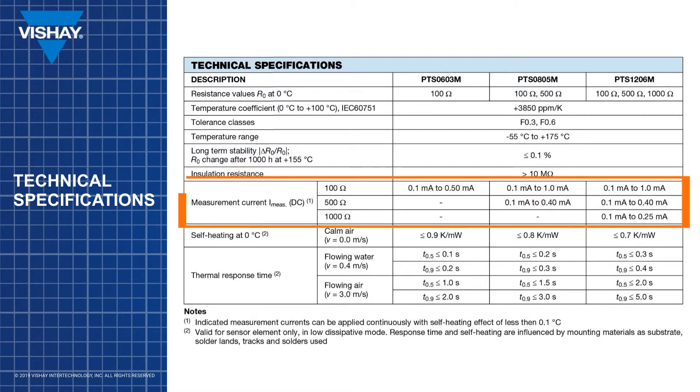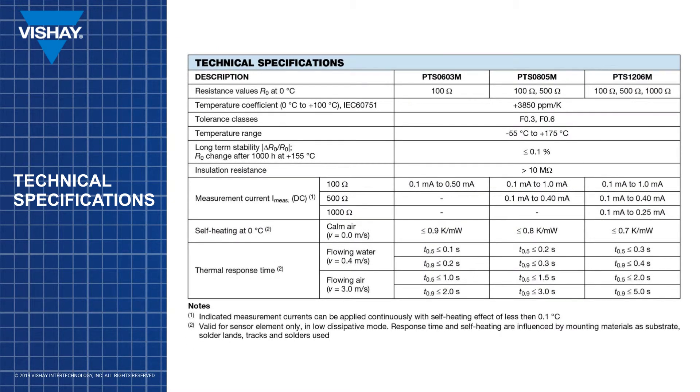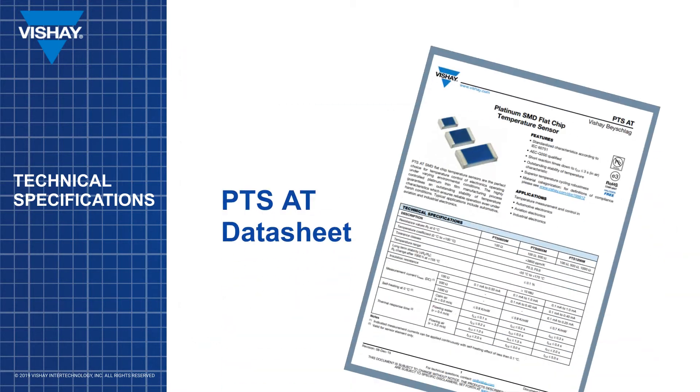The measurement current is dependent on the size and value of the sensor. The measurement currents listed can be applied continuously with minimum self-heating effects. The thermal response time of the sensor is less than or equal to 2 seconds in flowing air. To view the complete PTS-AT data sheet online visit vishay.com and enter PTS in the search box on the top right.